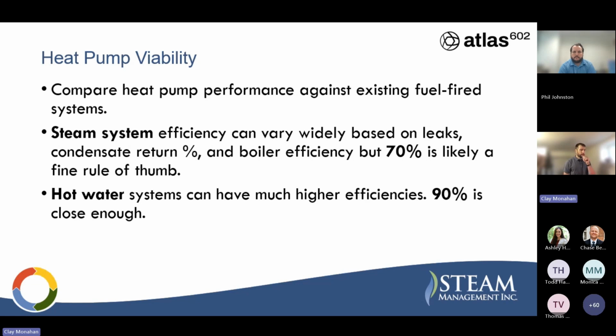Yeah, so that's a good question. I would say industrial heat pump is more a matter of the product you're selecting from. I think there are some that blur the lines, especially on the hot water application side, that could go into a commercial building or into an industrial facility. But there are dedicated industrial heat pumps or systems that use refrigerants like ammonia, or some of those open cycle systems like the MVR and the MVC. You're not going to see those in a commercial application. So there are specific heat pumps that are geared towards those industrial customers. But if it's a CO2 heat pump or a more traditional refrigerant like an HFO heat pump, those could be seen in either application, I'd say. Yeah, like ones that are geared towards process heating, right?